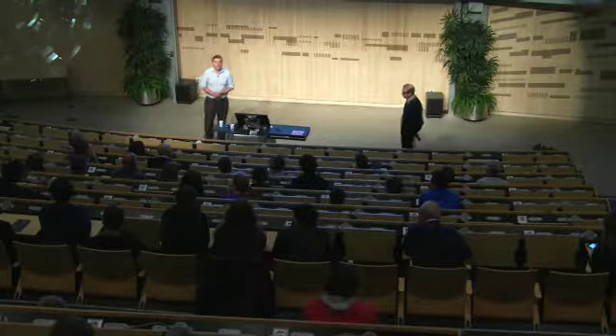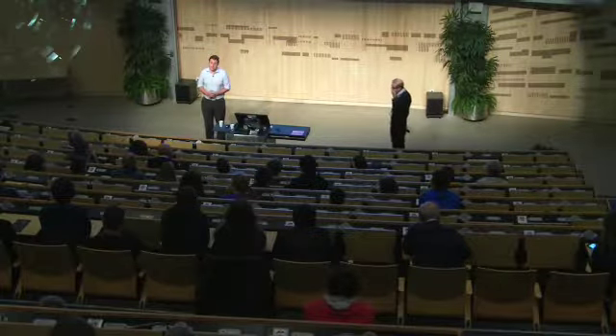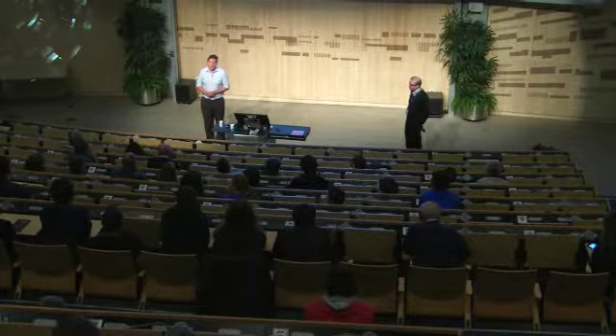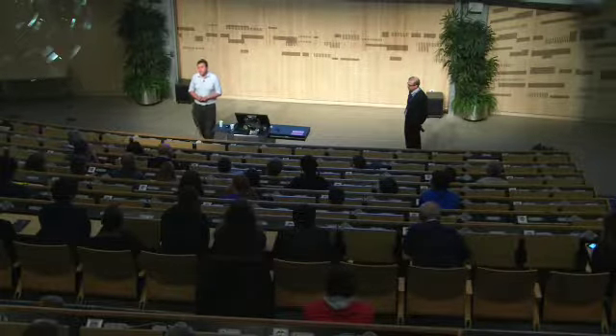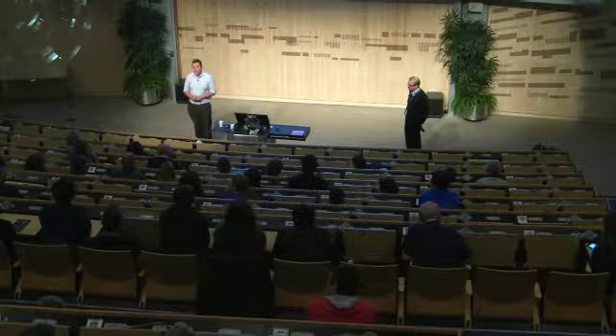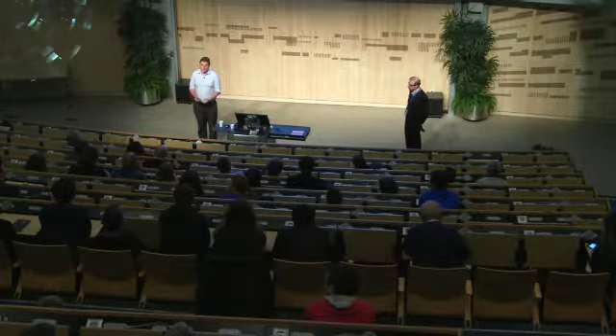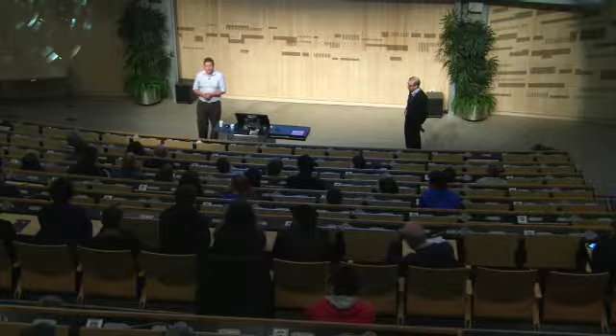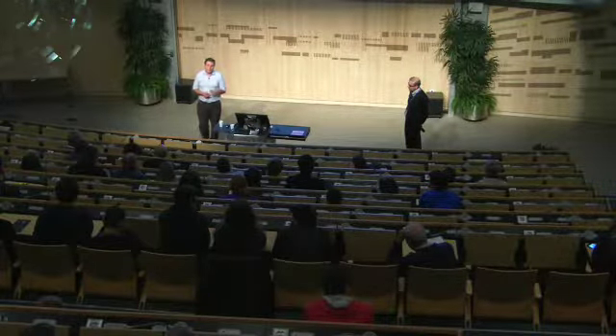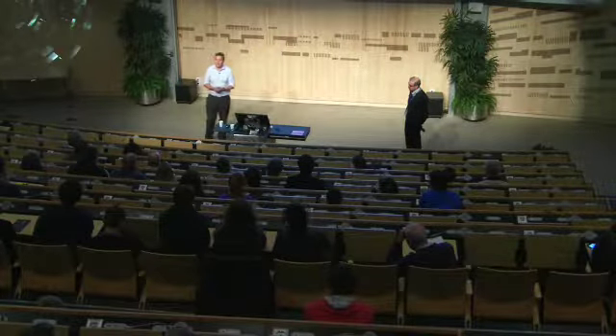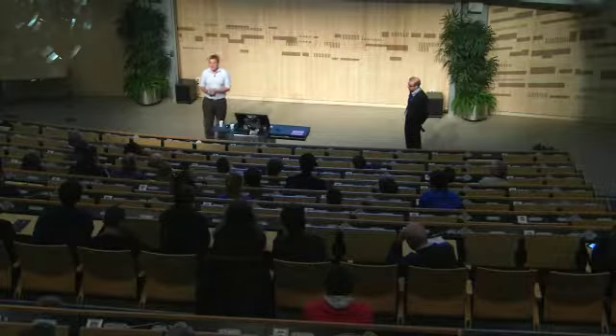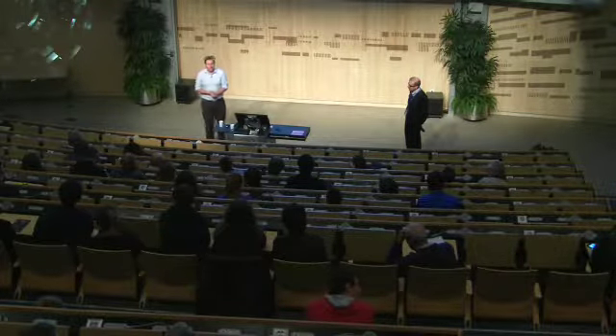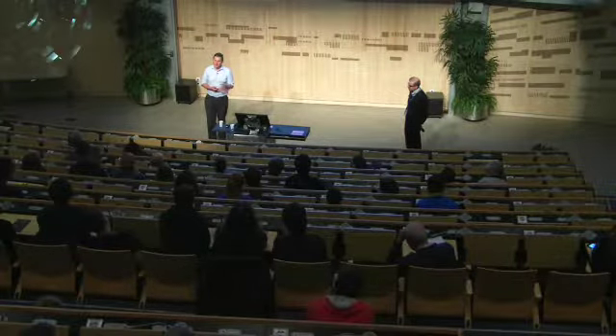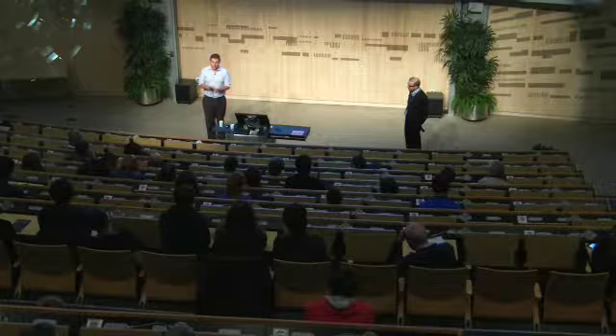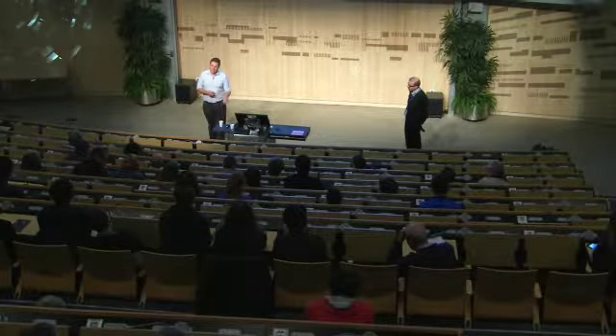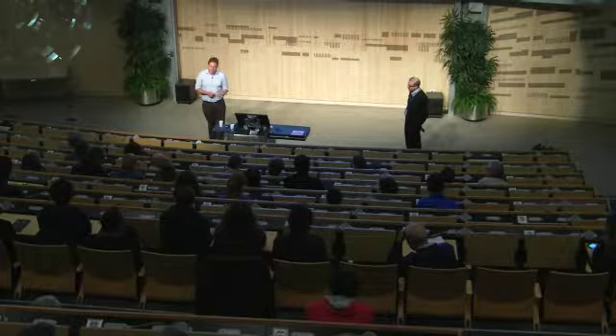Yeah, so what we do is we have a calibration phantom. So we actually start by knowing what materials we're looking for. And we can do up to 7 materials, but you need to know what they are to begin with. And usually that's actually a pretty reasonable thing because you know what you put in the animal or the specimen. It does fall over because we often just start with fat and water, and then something goes into the Perspex phantom, and depending on quite how the calibration's gone, it either gets assigned to fat or water or something. And if you start throwing in another material like fat, water and Perspex, they're so close that it actually ends up confusing the material decomposition routines. So yes, we calibrate on real materials knowing what they are.